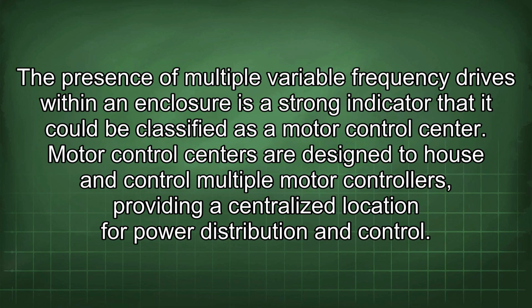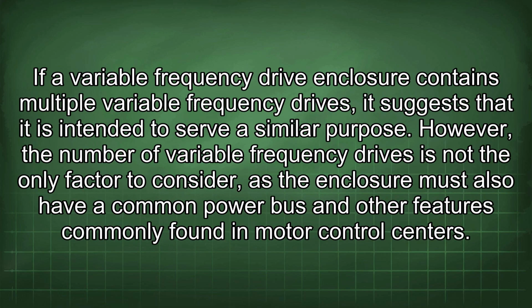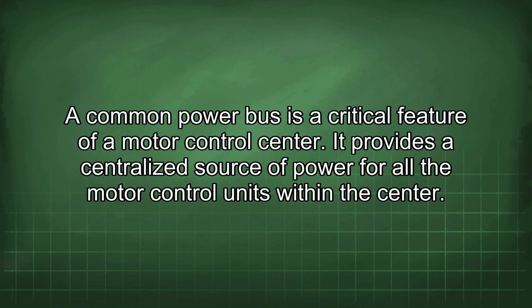The presence of multiple variable frequency drives within an enclosure is a strong indicator that it could be classified as a motor control center. Motor control centers are designed to house and control multiple motor controllers, providing a centralized location for power distribution and control. If a variable frequency drive enclosure contains multiple variable frequency drives, it suggests that it is intended to serve a similar purpose. However, the number of variable frequency drives is not the only factor to consider, as the enclosure must also have a common power bus and other features commonly found in motor control centers.